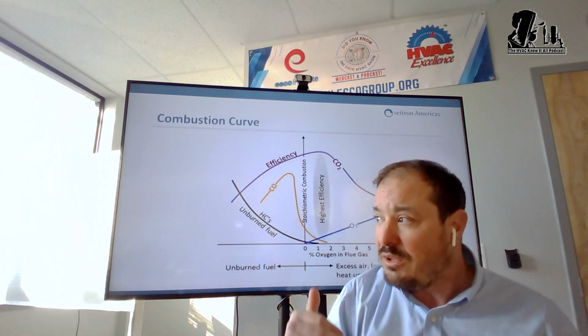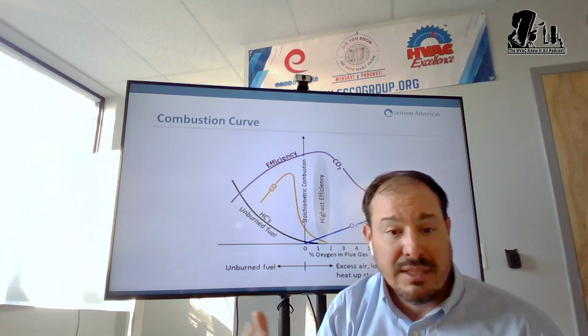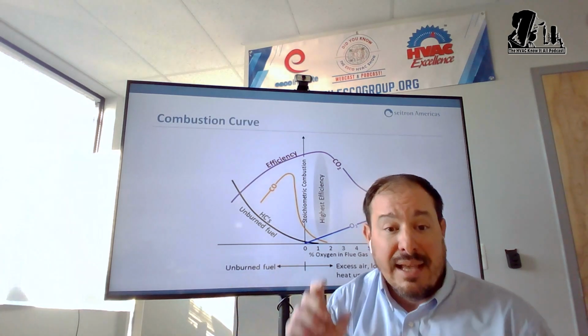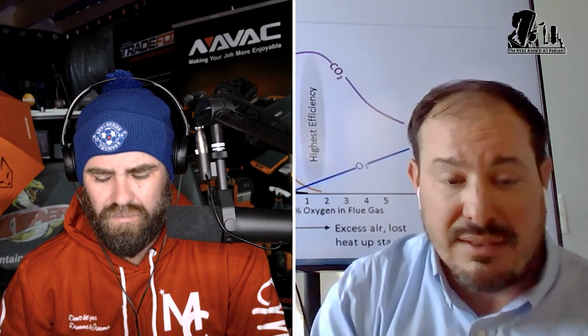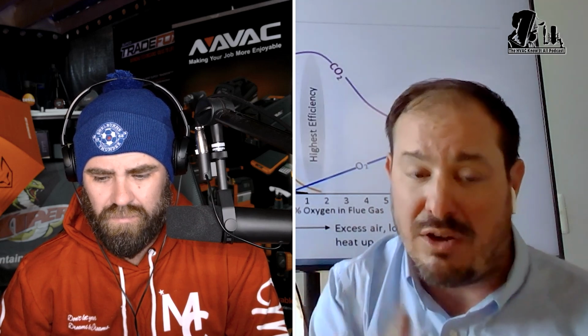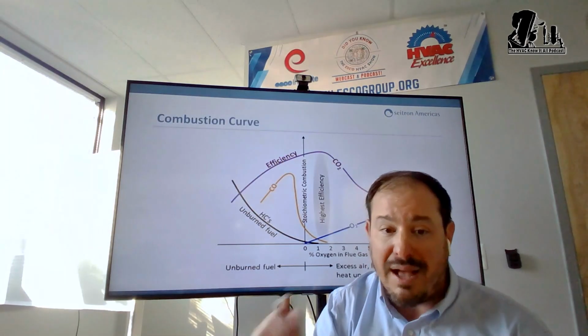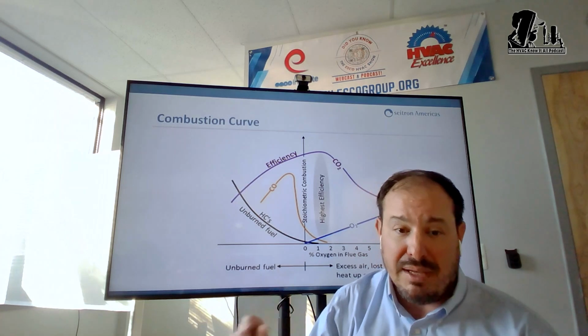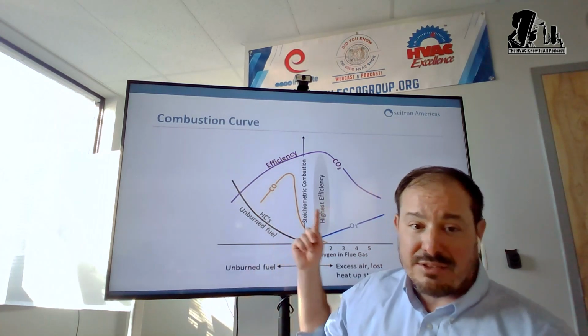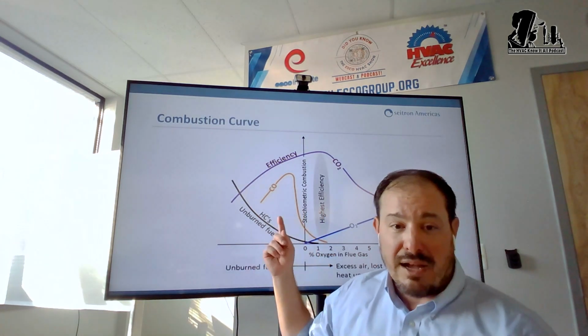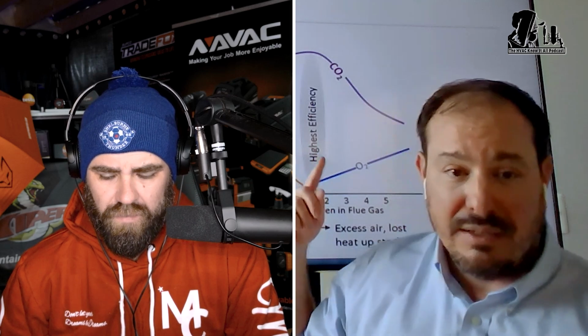And more and more manufacturers now, on the furnace and the boiler side, if you look at the setup guide or the installation side of the manual, they normally give you two numbers. Some will give you CO2, but they'll also give you either oxygen or CO to look at also. They don't just go by CO2 anymore. And the reason being, I want to make sure what side of the stoichiometric curve I am on. Makes sense. You could be on either side.